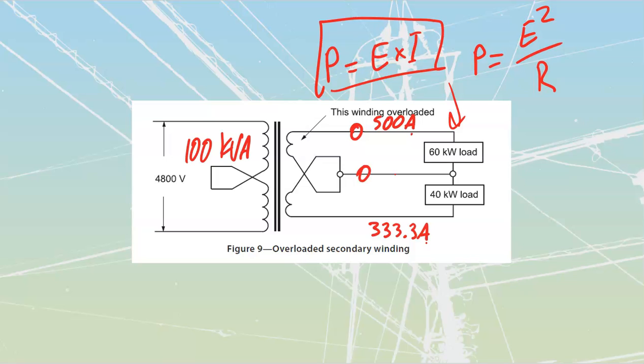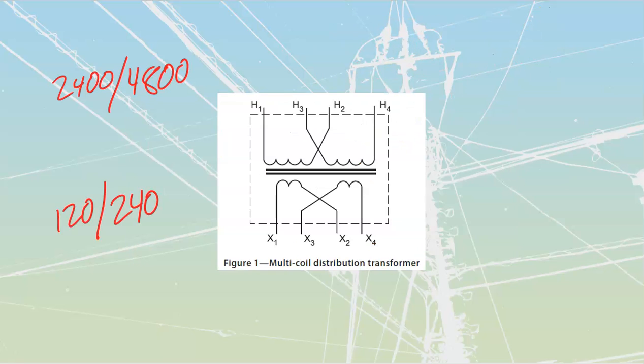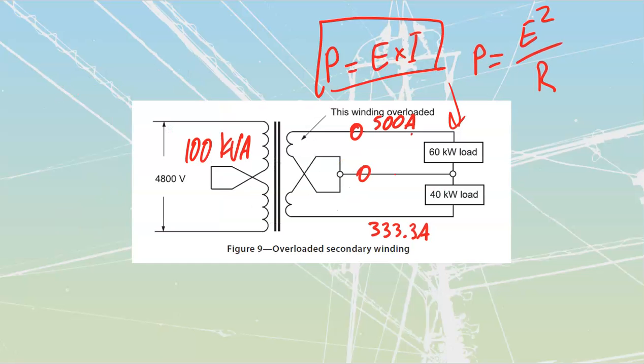Now, how many amps were each of these windings rated for? If you go back to what we took a look at initially, we took the 50 kVA, half of each transformer, and divided by the half voltage, and that gave us a grand total of 416.7 amps that they were each good for. So this one here is greater than what it is supposed to be carrying. Am I actually delivering a full 100 kVA or 100 kilowatts off of this thing? Absolutely I am. But this winding is going to be overloaded.